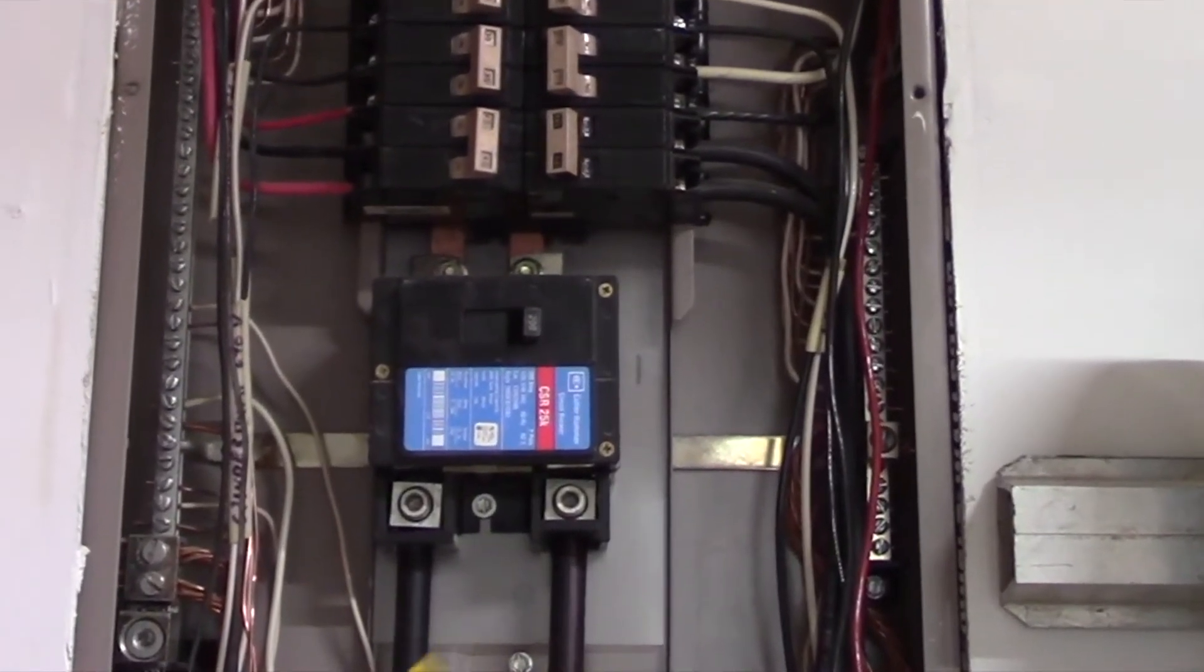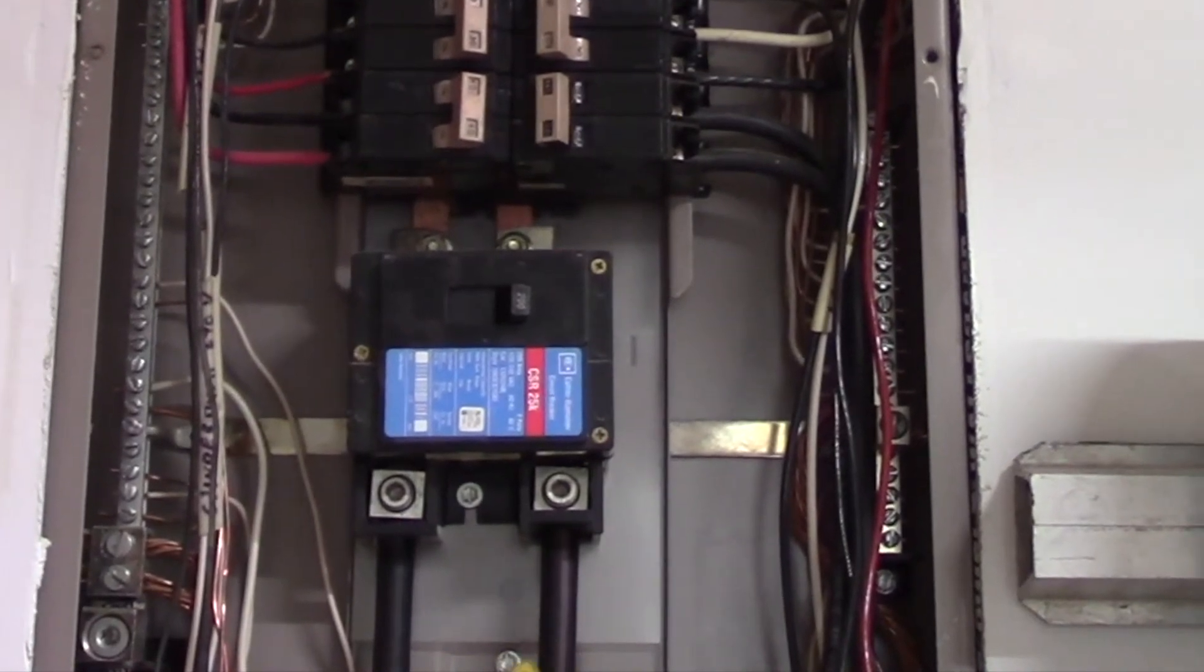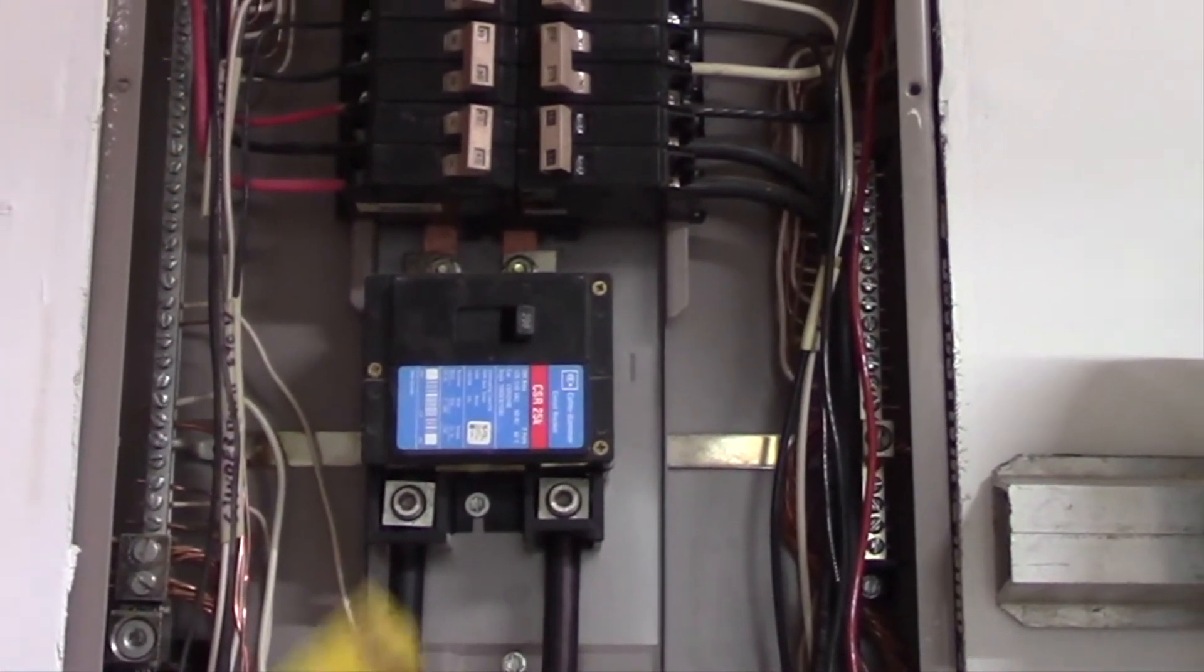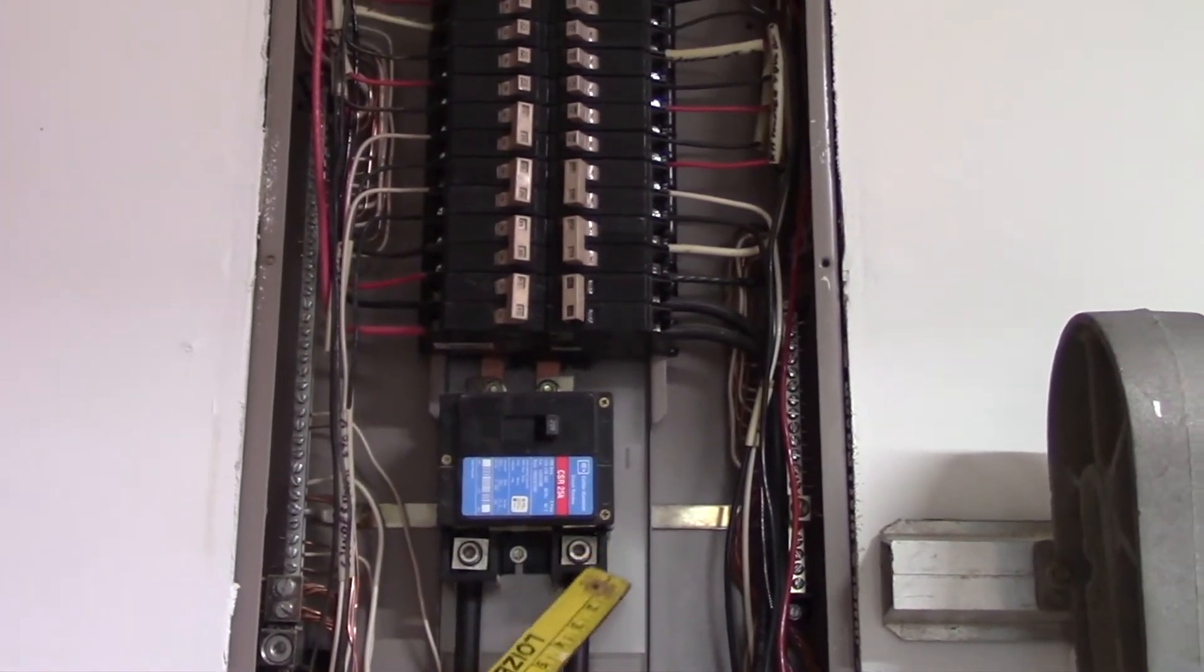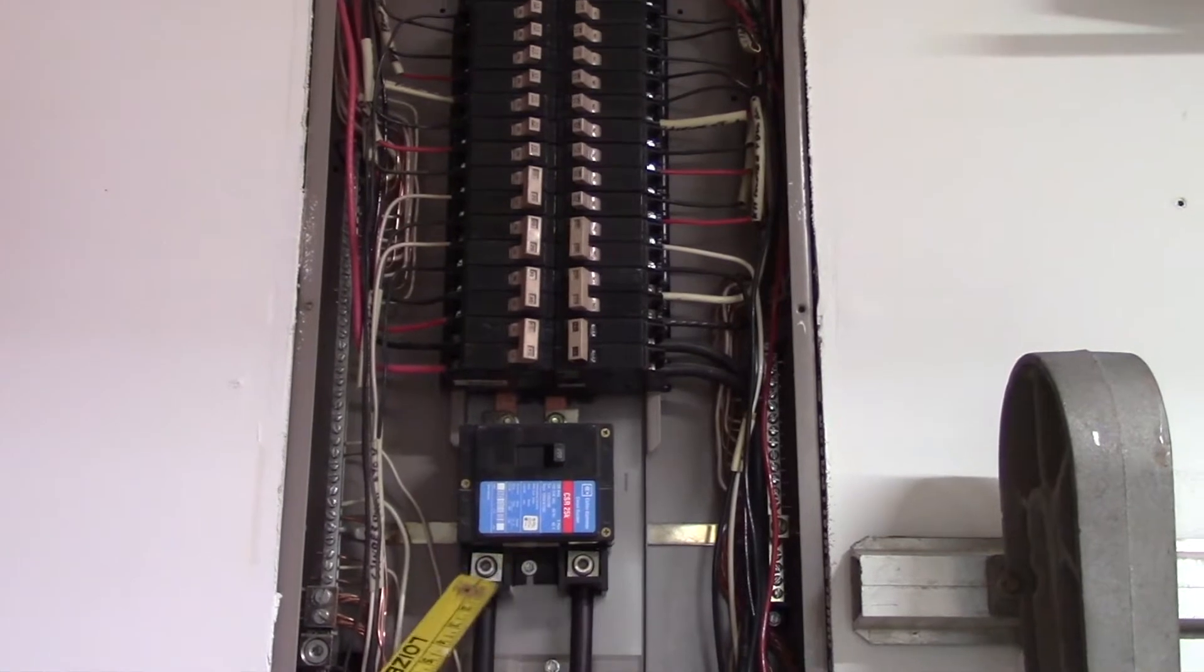These two wires here are the heavy wires that bring electricity into your home. Even if you shut off the main, there is still going to be electricity coming to these two terminals. There's no way to shut that off without removing the meter.